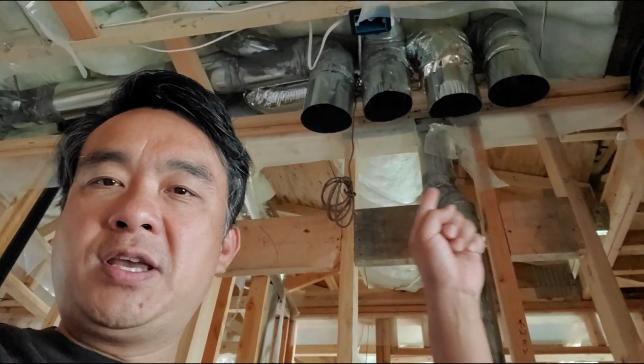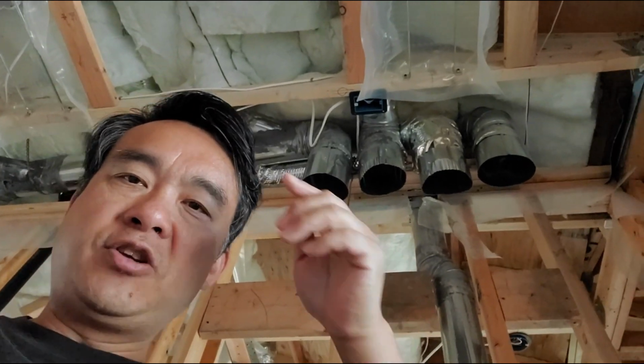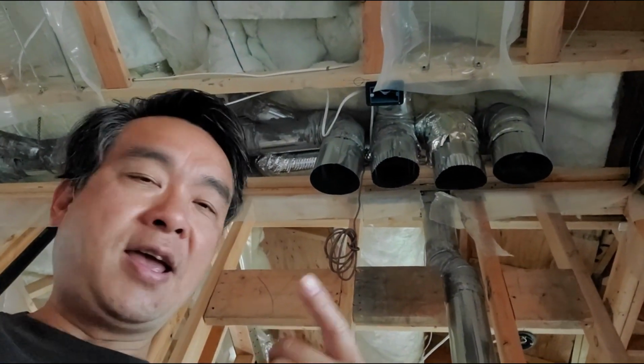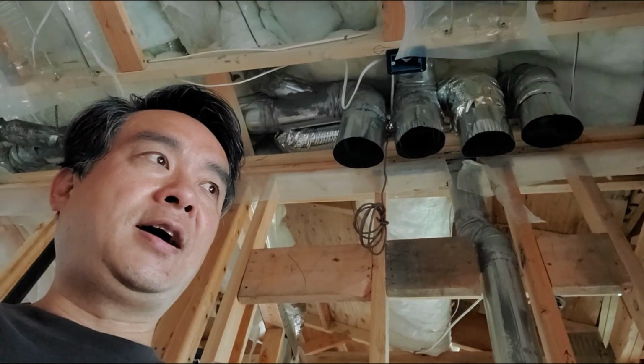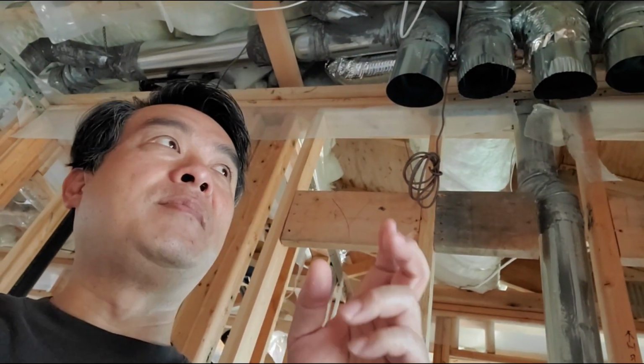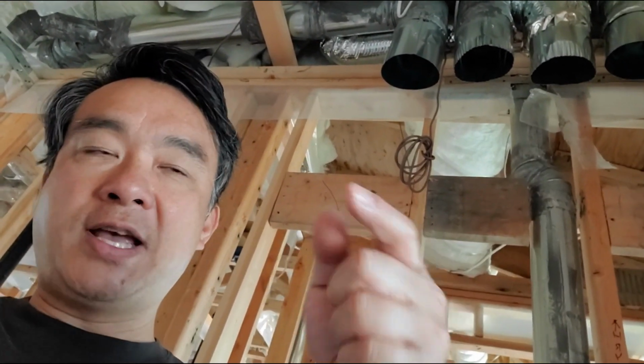Okay, what are these 3 turbo looking kind of vents over here? This is an HRV unit. It's basically an air recycle system where, so a house needs breathing, right? But if you have fresh air coming into the house and it goes straight back out, all that expensive heat that you heat up is gone to waste. It kind of blows out the window. What this does is that it's an air exchanger, meaning you take the hot air as you blow it out, you exchange it with the cold air coming in. You exchange the heat, so it kind of does a heat swap, and you don't lose heat that way. That's the HRV.